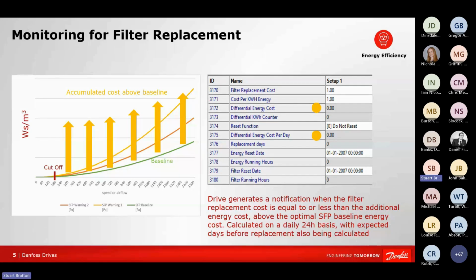So if the drive detects, well, hang on a minute, all of a sudden I'm now requiring more power to generate the same airflow, that indicates a problem, and it probably indicates that the filters in an air handling unit, for example, are starting to clog up.